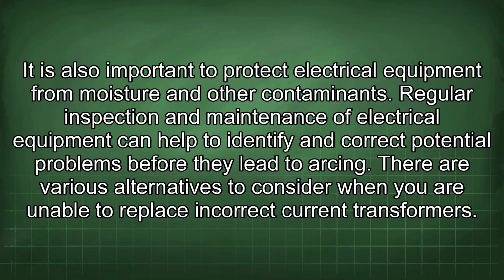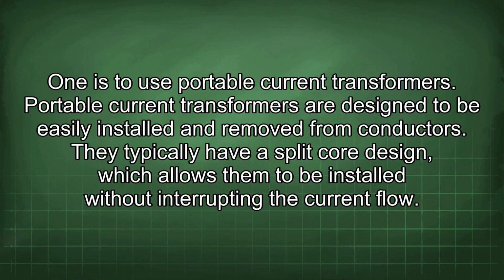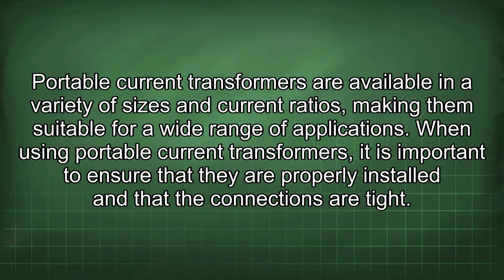There are various alternatives to consider when you are unable to replace incorrect current transformers. One is to use portable current transformers. Portable current transformers are designed to be easily installed and removed from conductors. They typically have a split core design, which allows them to be installed without interrupting the current flow. Portable current transformers are available in a variety of sizes and current ratios, making them suitable for a wide range of applications.